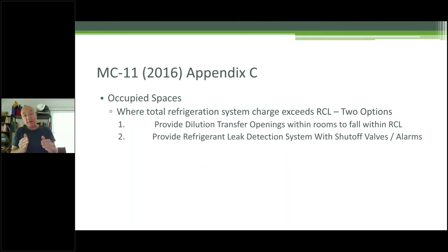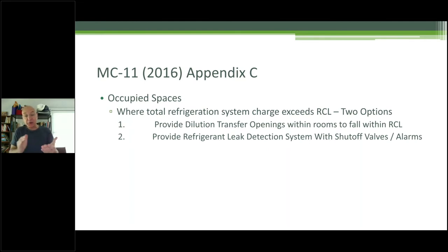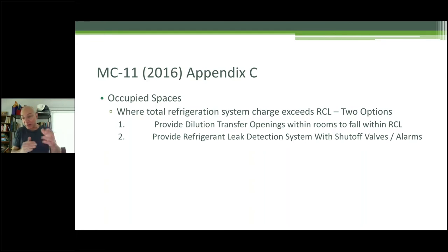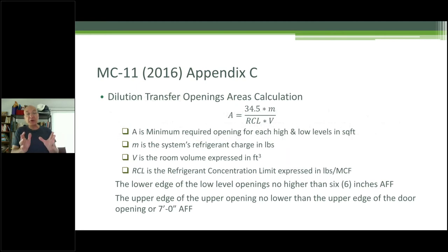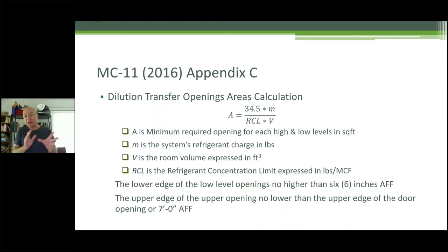Beyond that, we're going into occupied spaces. There's a new appendix in MC11 — the refrigeration chapter — for occupied spaces. When the total refrigeration system exceeds the RCL, you have two options: provide dilution transfer openings with rooms to fall within the RCL — that's the undercut portion we're talking about — or provide refrigerant leak detection systems with shutoff valves and alarms. We're no longer saying 50% — you're saying you can go up to the full RCL of 26 in one room. If you exceed that, you've got to provide dilution transfer openings.